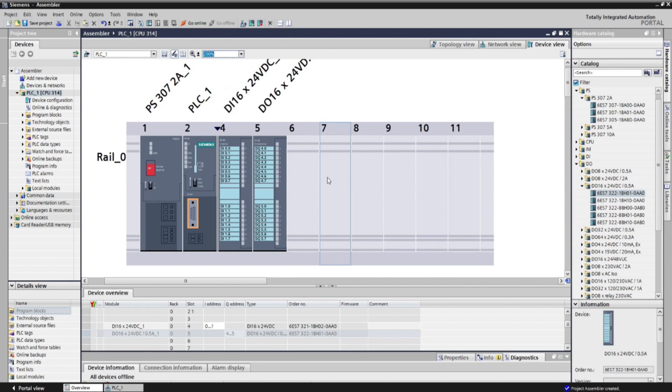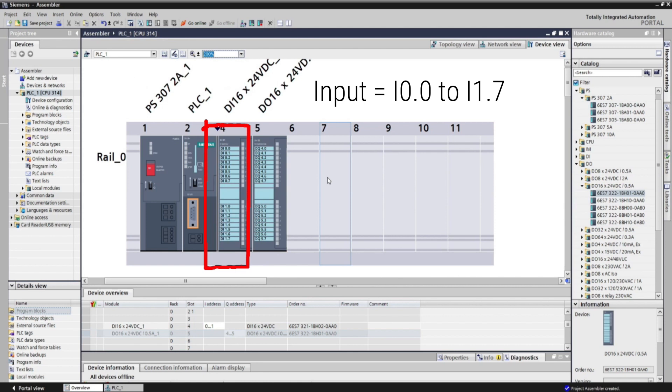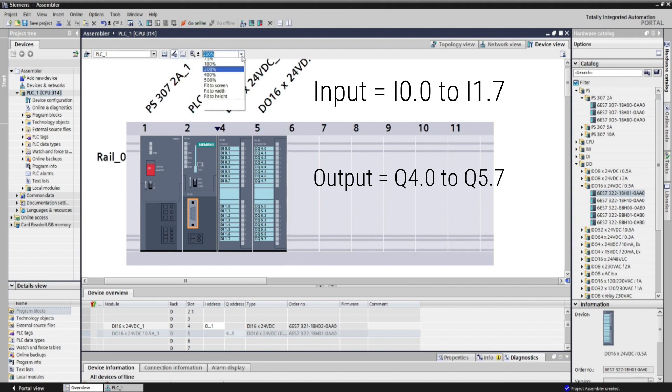Always take note about the IO tags of your module before making a program. The addresses of the input module range from input 0.0 to input 1.7. And for the output addresses, it starts with Q4.0 to Q5.7.